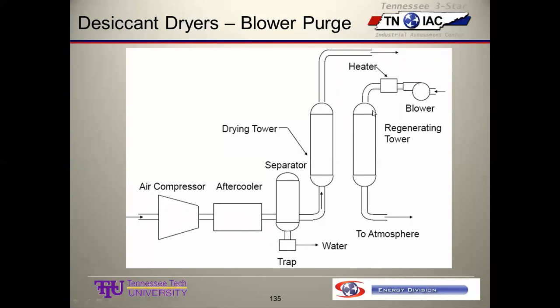So this is better. We have to put a little electrical energy into this, and then whatever our heating medium is, probably electricity, but it could be natural gas fired, or it could be a steam coil, whatever. And then this stream just takes air from the compressor room, goes through the tower and gets vented to atmosphere, taking all the moisture that we're pulling out of this tower and getting rid of it.